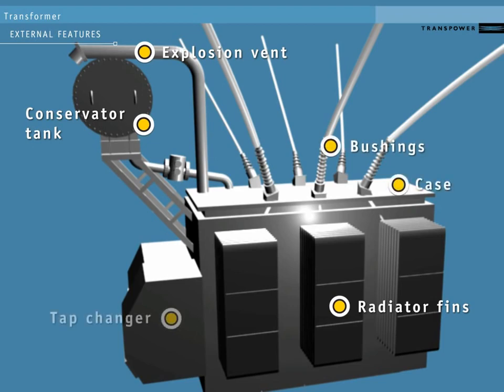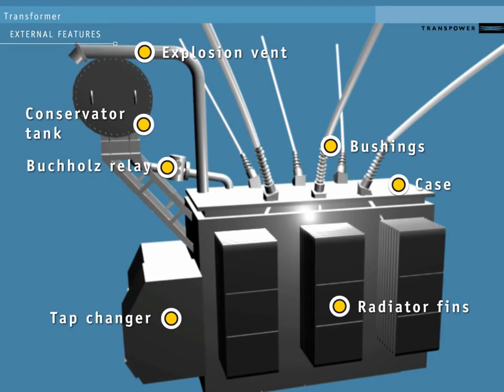The tap changer sets the exact amount of voltage change. The Buchholz relay lets us detect the presence of gas caused by the deterioration of the oil and/or a rapid increase of oil pressure.